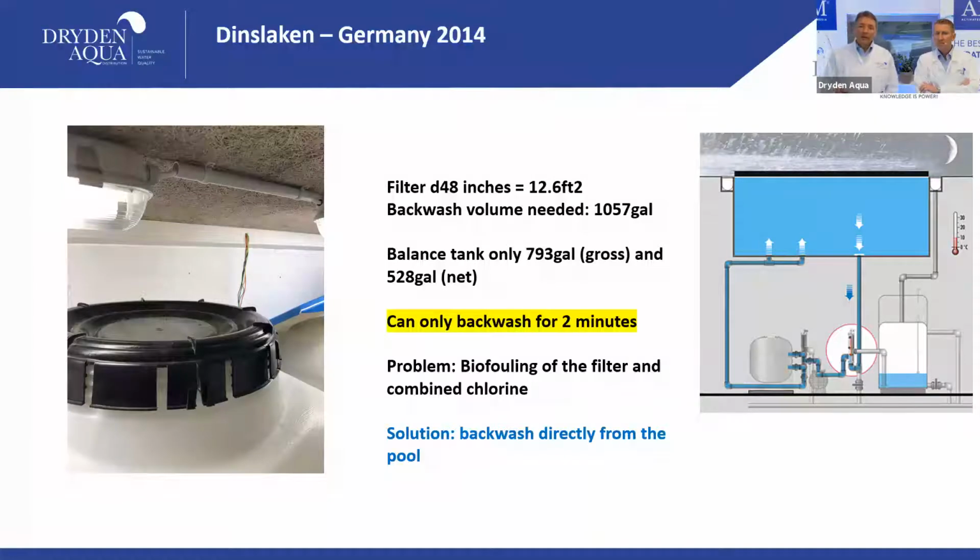What have we done? We took not the main drains, it was the suction side from an attraction, and with a butterfly valve or a valve, doesn't matter. So we took the water directly from the pool so we could backwash 5 minutes, and that really solved the problem. So 2 things, these diffusers and that solved the problem. And then we were absolutely okay with combined chlorine.